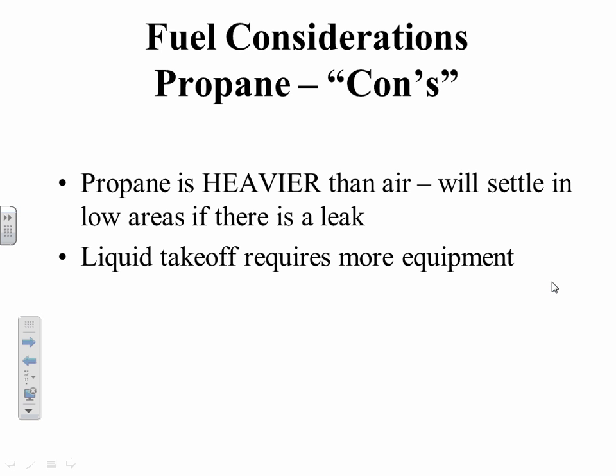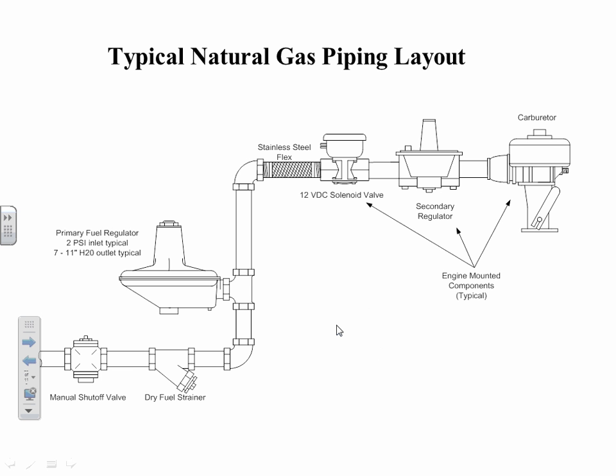We even had a railroad company that came back with a story too, that they actually located the generator set in a low area, and they had a leak there, and it took it out, but nothing else. They had put it at the bottom of this little bowl type area. So they relocated and bought a new set. So it's heavier than air. That's very dangerous. Liquid takeoff requires a little more equipment. They've got vaporizers and things like that. So not much on the con side, but just have to watch it where you put it.